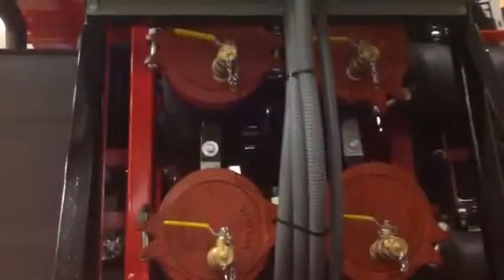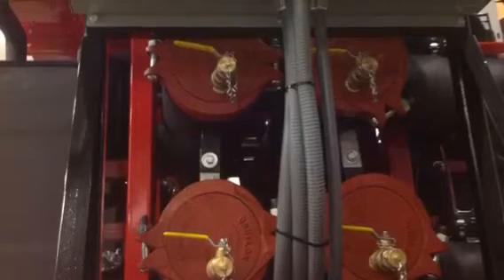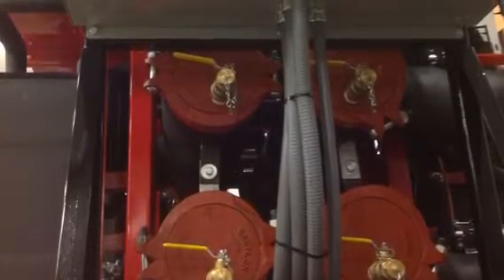This still shot shows the seal-tight coming down through the red frame and then passing in between the headers to the opposite end of the junction box. This is the view of the 4 sets of seal-tight, which are the power for each of the 3 modules. The 4th is routed for control power to the master controller.